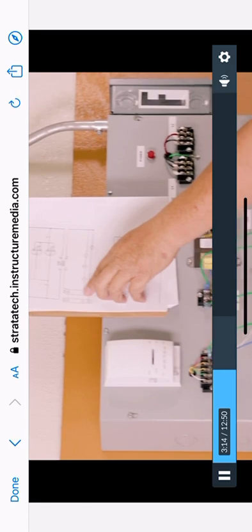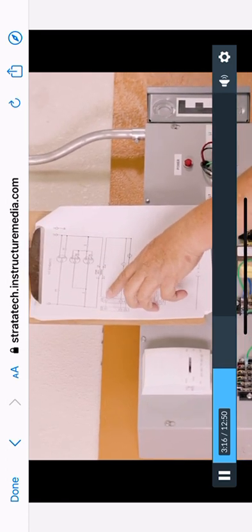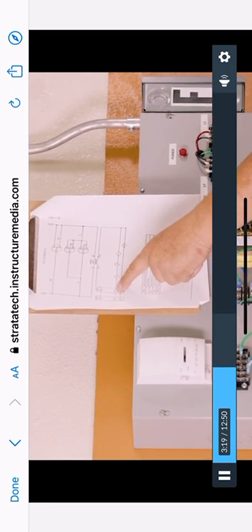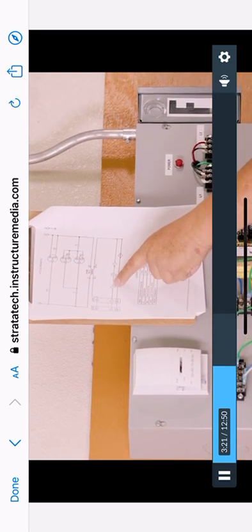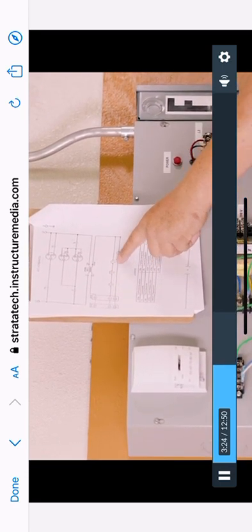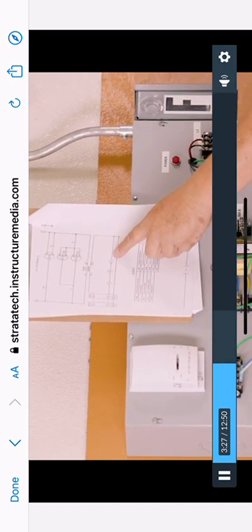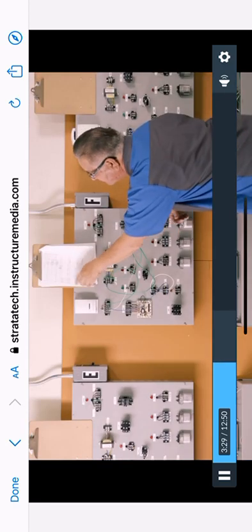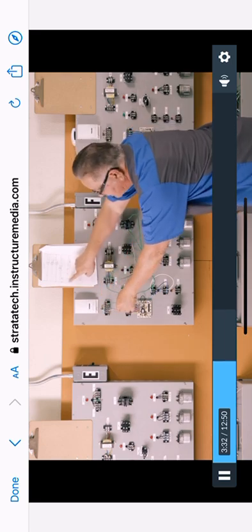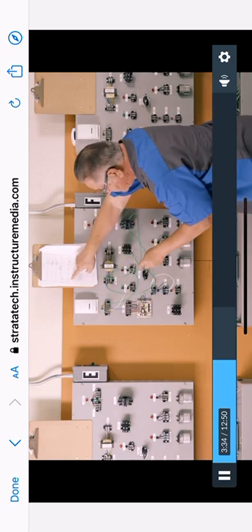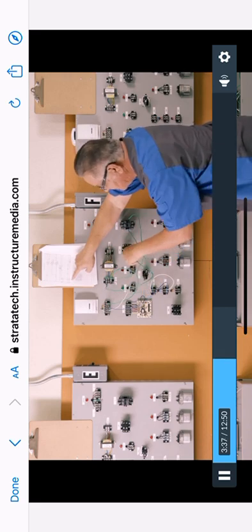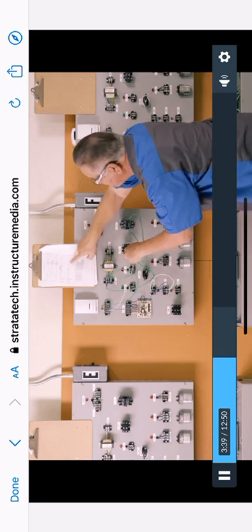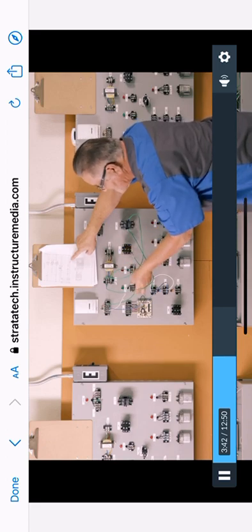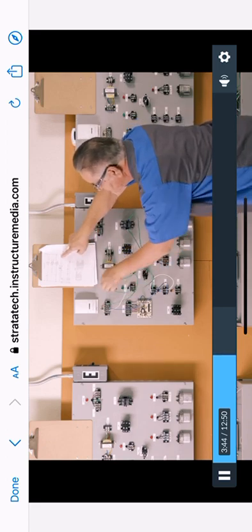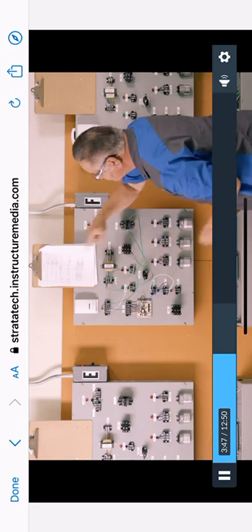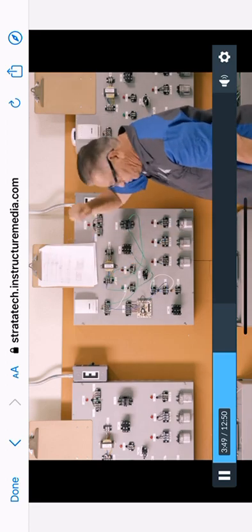So I just completed this red circuit to the 24 to the R terminal. I just completed my cooling circuit, which is the yellow one, from the Y low pressure switch to the high pressure switch to the contactor coil. I came out of my contactor, went to my common. Now I went from my green, which is this one here, my G circuit. I went straight to my indoor fan relay coil, which is this one here, the white wire. I came out of the indoor fan relay coil and I went back to my common, which is right here. So I just completed that. Now we're going to do the high voltage.